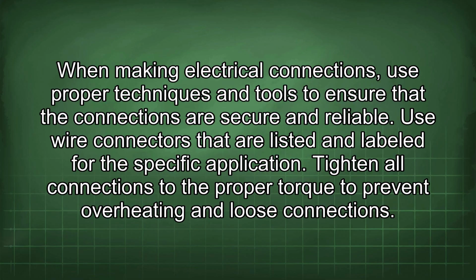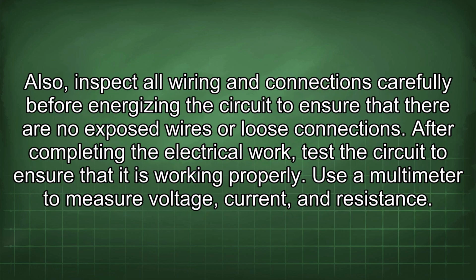Use wire connectors that are listed and labeled for the specific application. Tighten all connections to the proper torque to prevent overheating and loose connections. Also, inspect all wiring and connections carefully before energizing the circuit to ensure that there are no exposed wires or loose connections. After completing the electrical work, test the circuit to ensure that it is working properly.